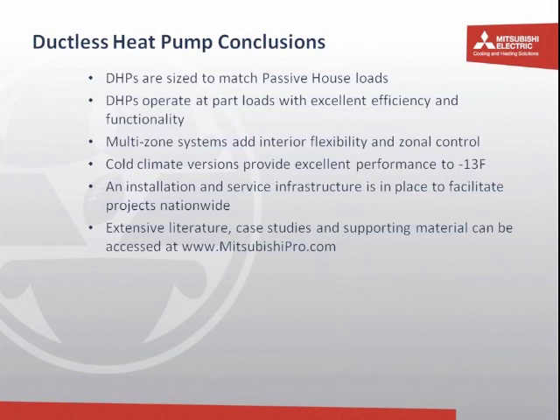In conclusion, the ductless heat pump, we believe, provides an excellent solution that enables you to match the very minimal heating and cooling loads of a passive house to a system that's able to both scale down to that size and then within the range that the house is going to operate, perfectly match the load that exists. They operate at part load with extremely high efficiency and do so without losing any dehumidification capability or the ability to continuously keep the airflow circulating and the house comfortable.